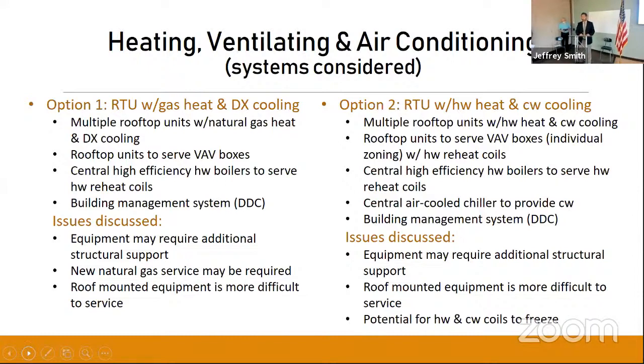The first option we looked at was rooftop units with all gas-fired heat and DX cooling. That would eliminate the need for a central chiller plant — all the cooling would be done at the rooftop unit, and a majority of the heating would be done at the rooftop unit through gas. We would also have VAV boxes in the space to give you zoning for the different areas, with hot water reheat coils, so you'd have small boilers to serve those reheat coils.